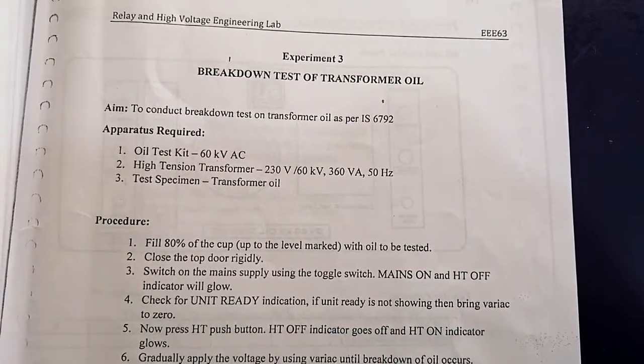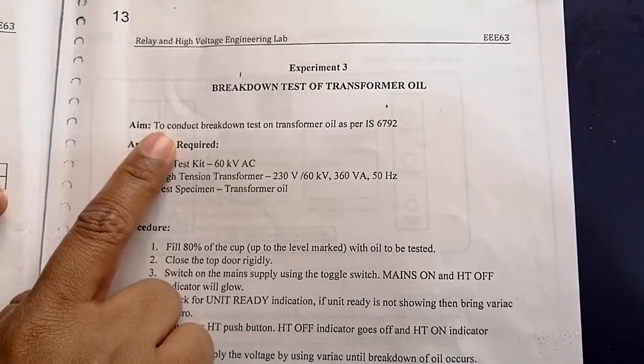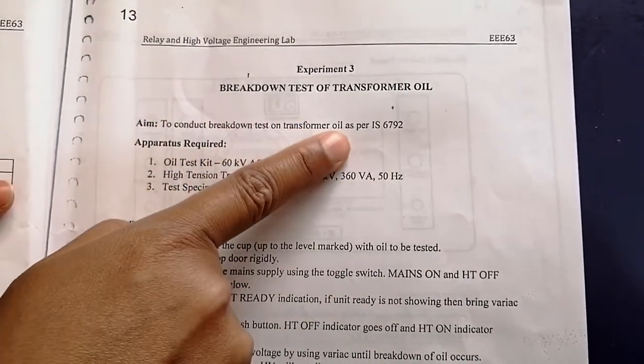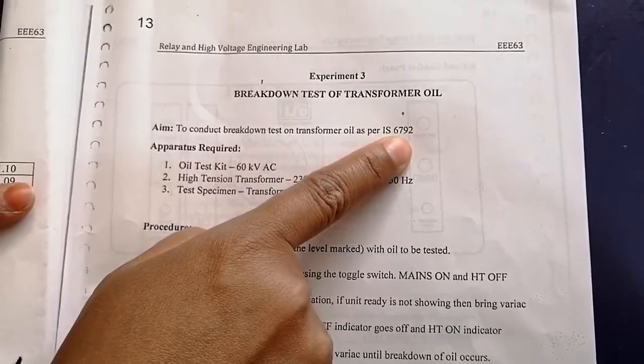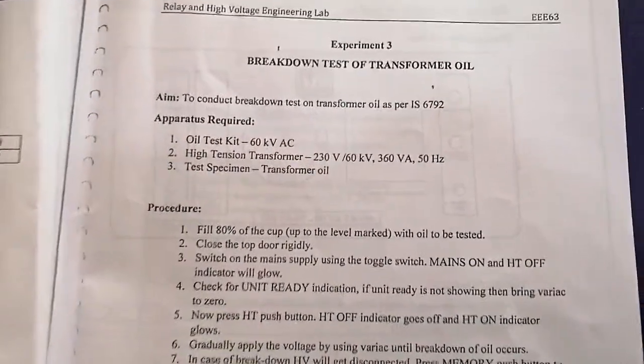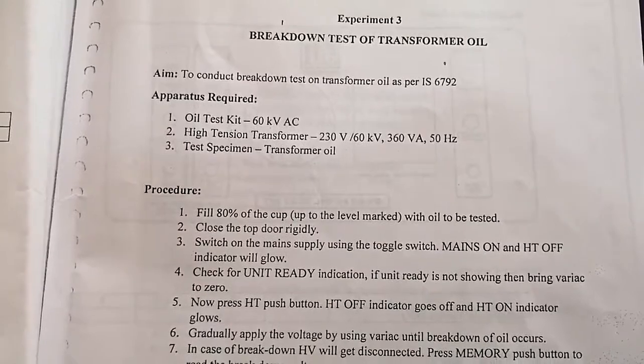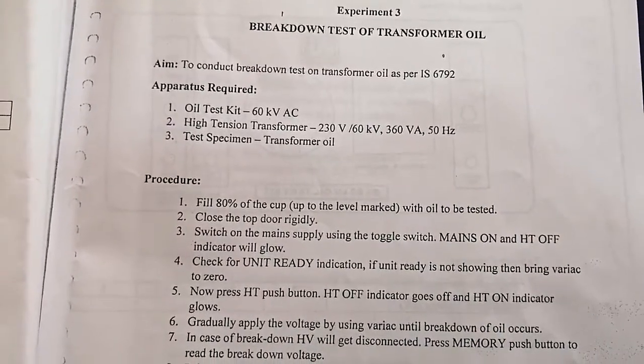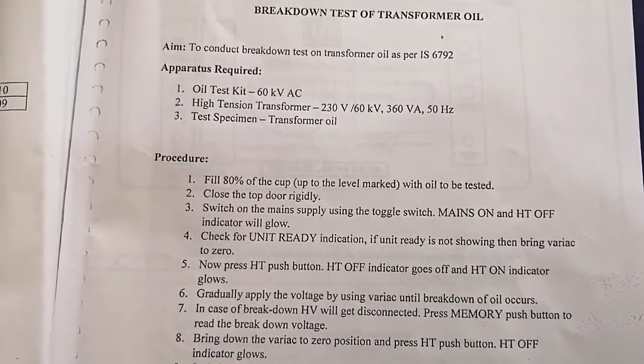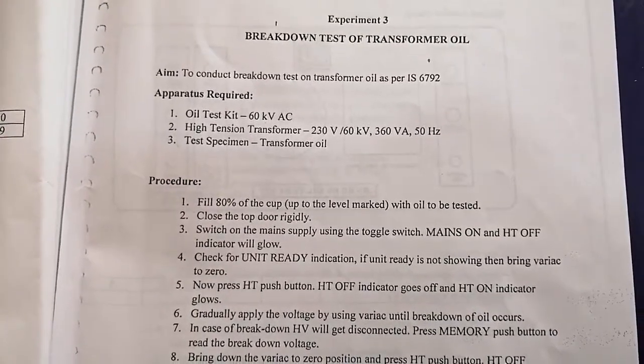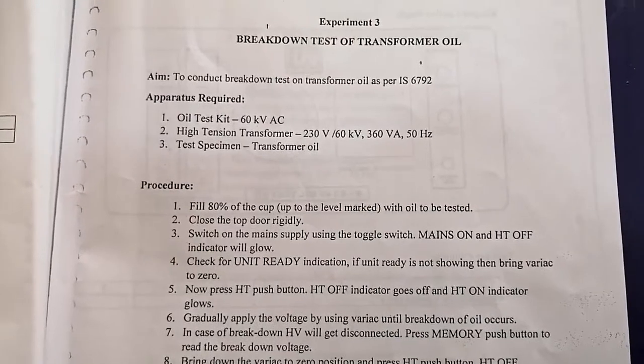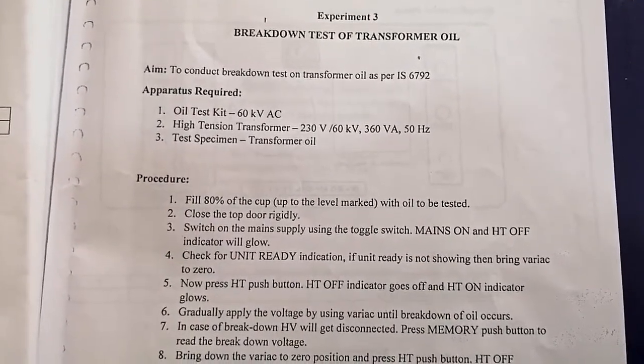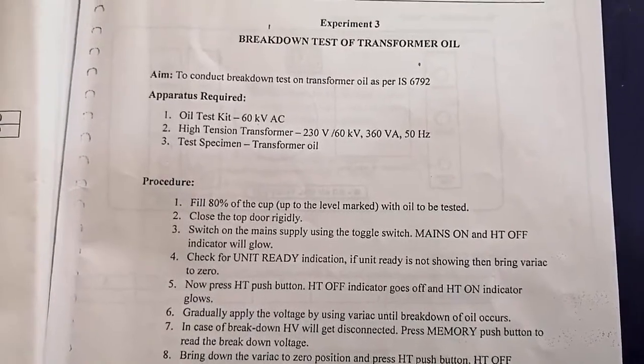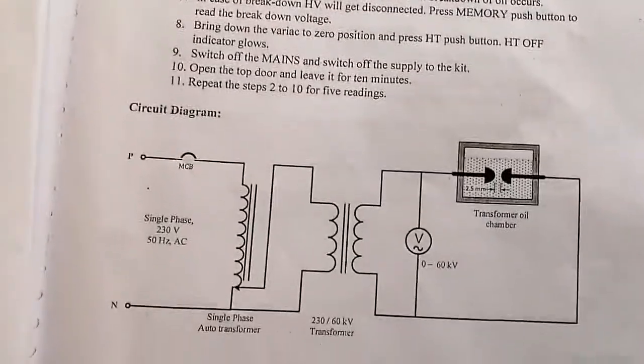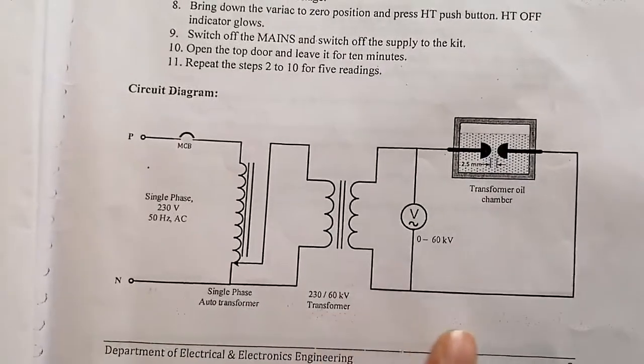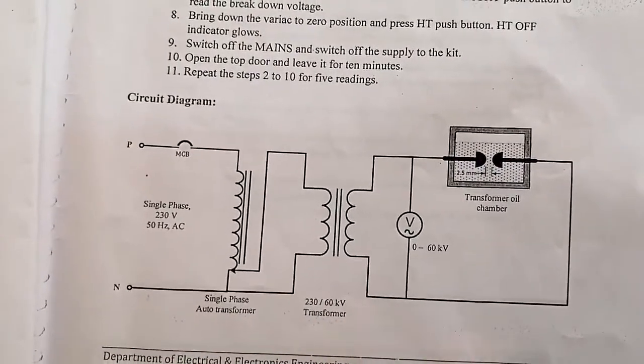This is the breakdown test of transformer oil. Aim of the experiment: to conduct a breakdown test on transformer oil as per Indian Standard 6792. Why do we have to do this experiment? In order to test the transformer oil breakdown strength, because transformer oil is used as a cooling oil for the purpose of reducing the temperature in a transformer or in any electrical device where transformer oil is used as a cooling material. So in your lab, this is the circuit diagram for the breakdown test of a transformer oil.